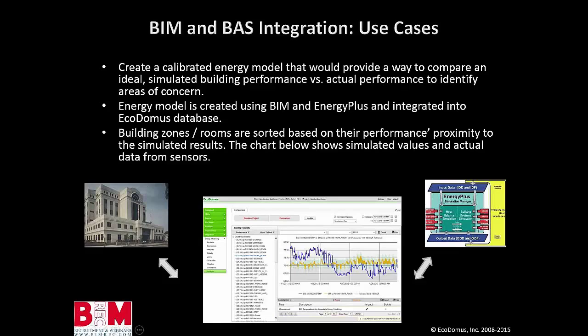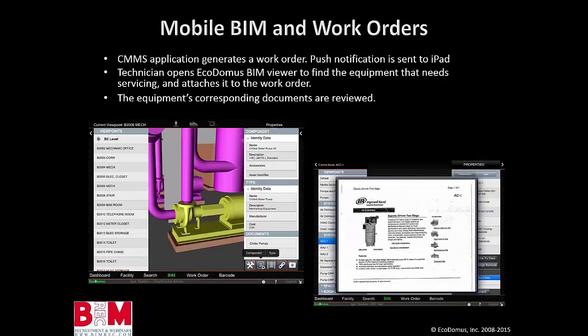And in blue, we see the data from the actual sensors, explaining that for this particular room, which is room 1046, the values are significantly different. You know, they overlap only 20% of the time. So something is wrong here, either with the sensor or calibration, or maybe some dampers don't work properly. So it allows you to pinpoint the energy problems more efficiently than just analyzing it otherwise.